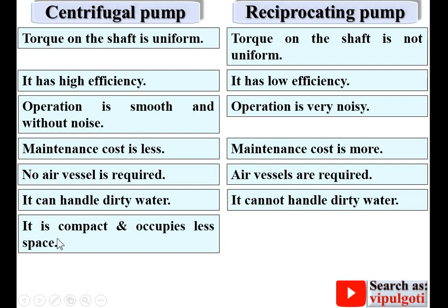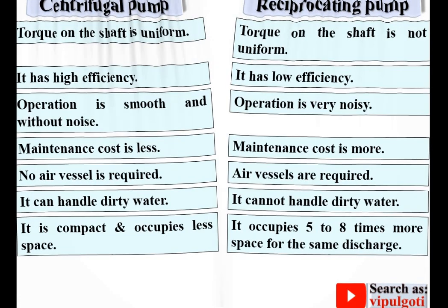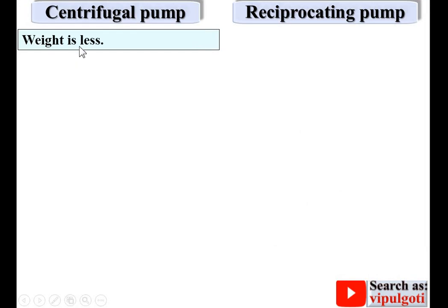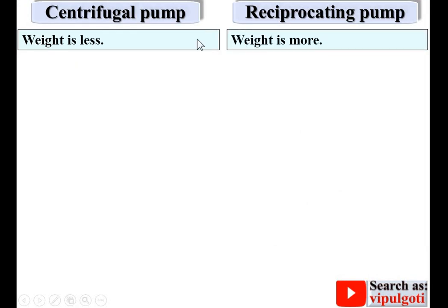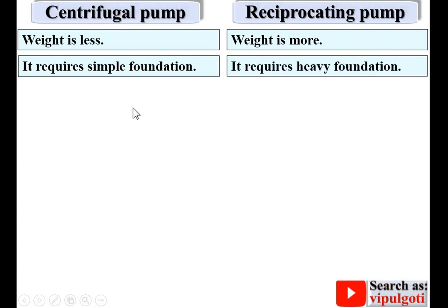Centrifugal pump is compact and occupies less space, whereas reciprocating pump occupies 5 to 8 times more space for the same discharge. Weight of centrifugal pump is less compared to reciprocating pump for the same power. Centrifugal pump requires a simple foundation, while reciprocating pump requires a heavy foundation due to its to-and-fro motion.